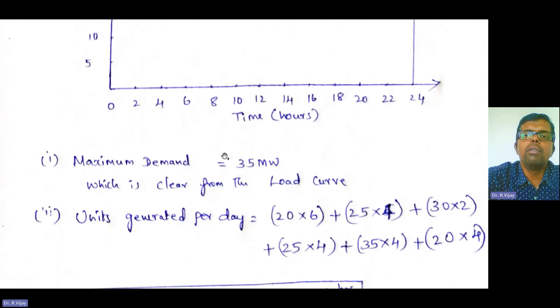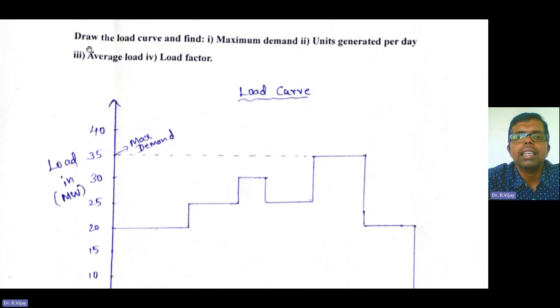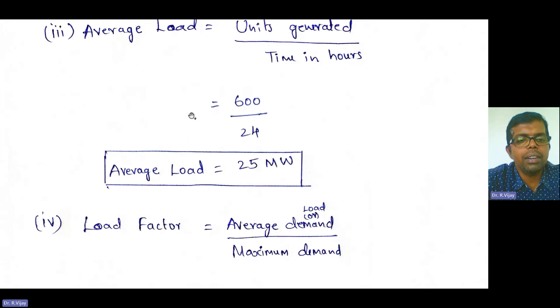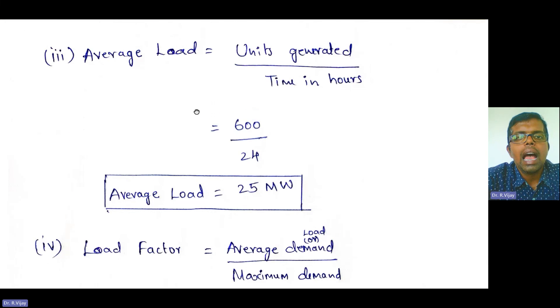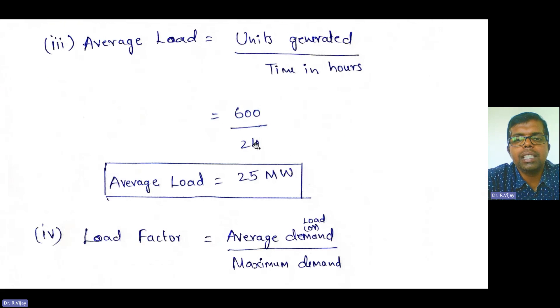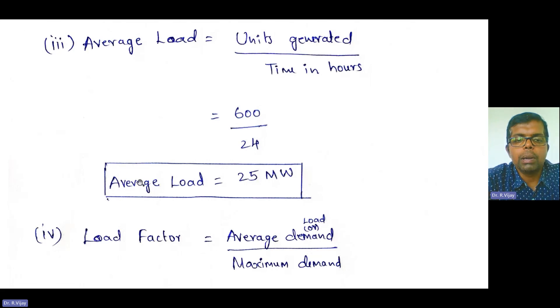Average load, or average demand, is equal to units generated divided by time in hours. So 600 divided by 24 equals 25 megawatt. The average load or average demand is 25 megawatt.